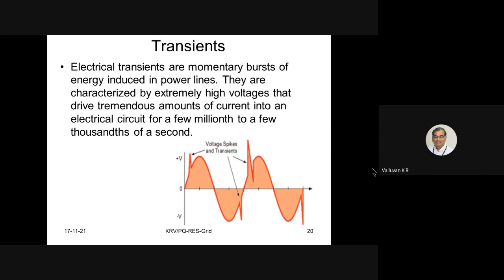I request you to switch off all the loads and remove the power socket plugs from the socket, because you might have observed that when there is lightning in a nearby place, the TV is gone. So equipment fails because of high transients. Transients are momentary bursts of energy induced in power lines. They cause equipment failure. It's okay if it is a TV.